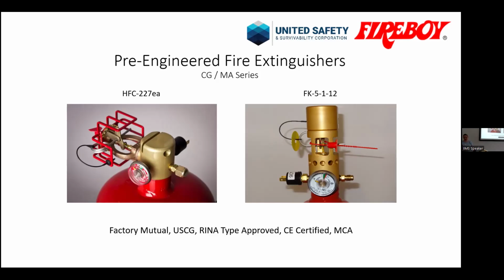Each extinguisher will come with a pressure gauge. So one of the main checks is to make sure that the pressure gauge is in the green range. That's an indication of being within the pressure. If it's going into the red a little bit, that's okay. Obviously, these are filled at 20 degrees Celsius, so not much in the UK, but in some hot countries the temperatures inside the engine room could sometimes be driven up. But we always fill at room temperature. We have specific environments, so we have heaters and ventilation to allow us to fill at the exact temperature, so it is always within the right range. When the cylinder is empty, the gauge will go straight to zero, and you know you have an issue.